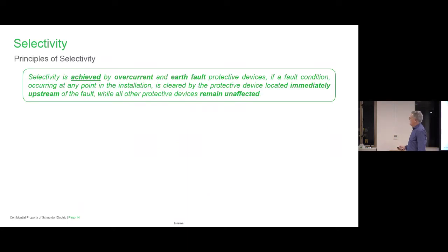So I'll move on now. Thank you for your question, that was great. This is really the start of where we're going: selectivity, which is effectively discrimination. This is a good definition, if you don't mind me reading it. Selectivity is achieved by overcurrent and earth fault protection devices. Let's say overcurrent, because earth fault can be dealt with by earth fault relays. If a fault condition occurs at any point in the installation, it is cleared by the protective device located immediately upstream of the fault, while all other protective devices remain unaffected. We called that total discrimination in the past. Now we call it total selectivity, but this is our goal.